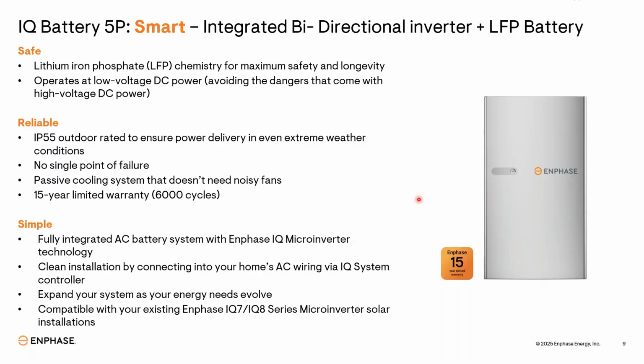You do not need to change your controller or your inverter, like in DC coupled systems. Because in a DC coupled system, once you install your stacking there, there is no chance of increasing the backup power. You need to change the inverter capacity there. But here it is easy for you. Batteries are compatible with both our inverter generations, IQ7 or IQ8. If you have a pre-existing site with IQ7, you can add these batteries there. Or if you're going with a new installation with the IQ8 series, you can also add these batteries.